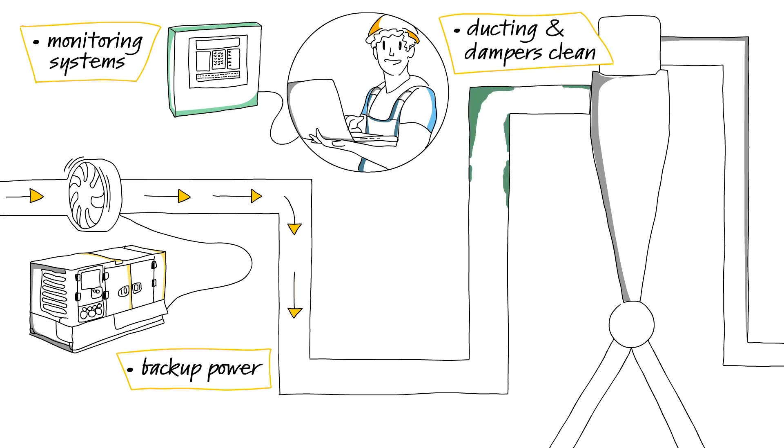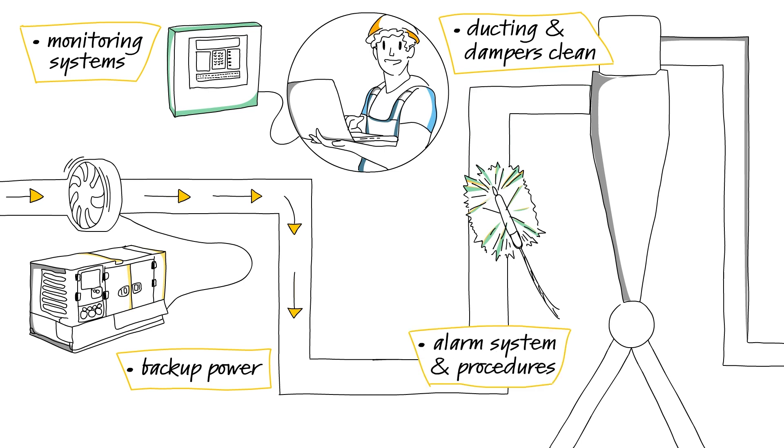Carry out periodic inspections. Keep up with ongoing maintenance, including cleaning, to prevent unwanted debris buildup where syngas can be produced and accumulate. Design your alarm system and procedures to ensure control room operators can respond effectively. Make sure alarms are easy for operators to understand. Periodically review your systems and procedures to ensure they are effective.